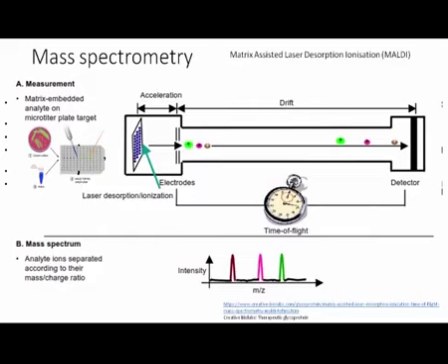There are other methods of ionization. Here laser is used, somewhere else a spray of electrons is used, somewhere else some other technology of ionization is used, and all of them essentially define the mass by charge ratio, and then depending upon the size of the molecule, each one of those charges will reach the detector at different times, and depending upon these different times they detect the mass.